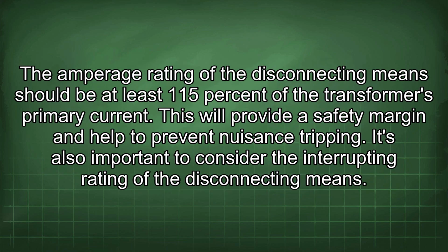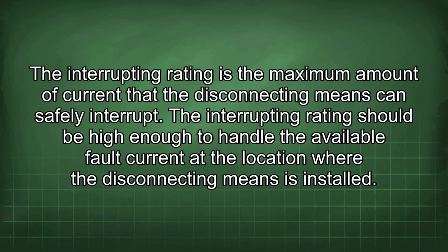The amperage rating of the disconnecting means should be at least 115% of the transformer's primary current. This will provide a safety margin and help to prevent nuisance tripping. It's also important to consider the interrupting rating of the disconnecting means. The interrupting rating is the maximum amount of current that the disconnecting means can safely interrupt.